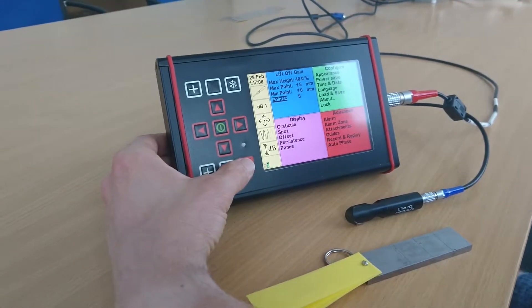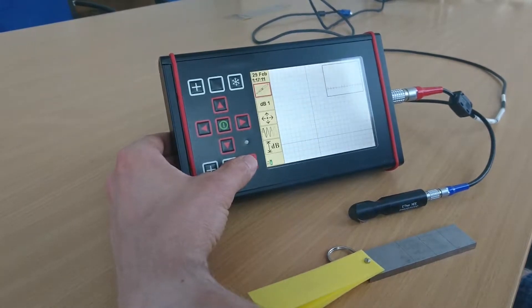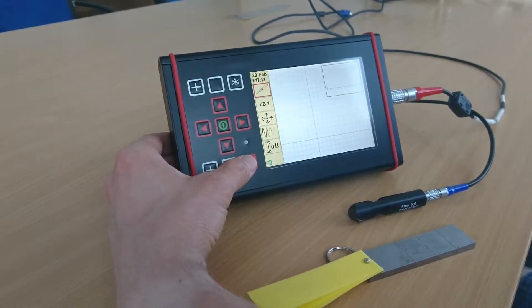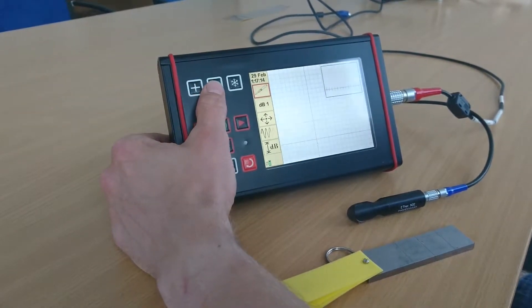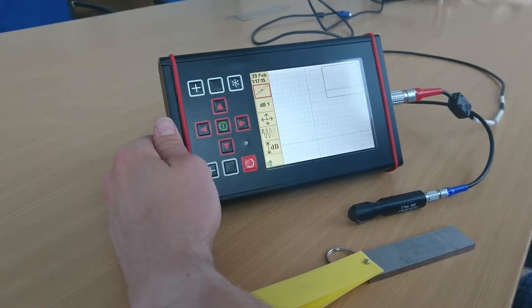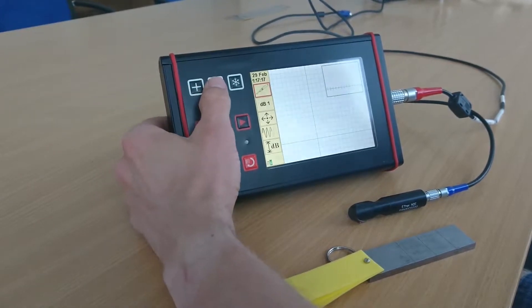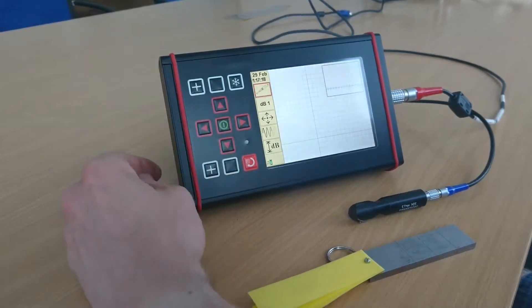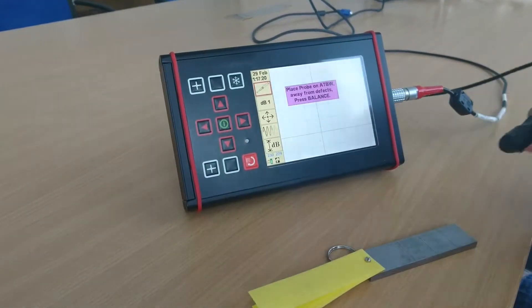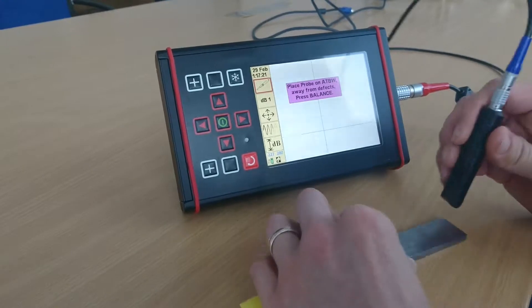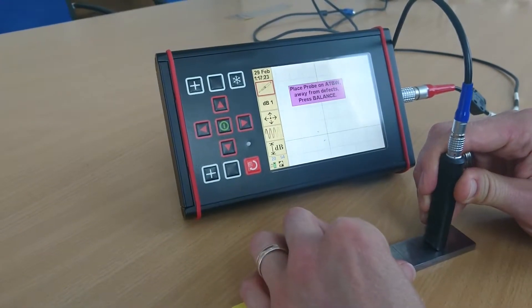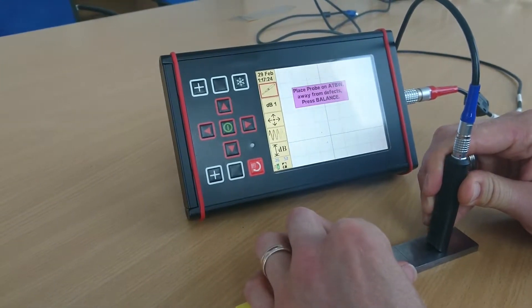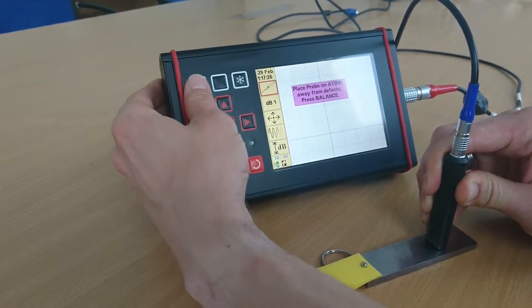So from there, go to the real-time screen. I've programmed the top blank key here with the lift off gain function. So push that to begin. I've taken my probe onto my test block, find a good piece away from a defect and balance.